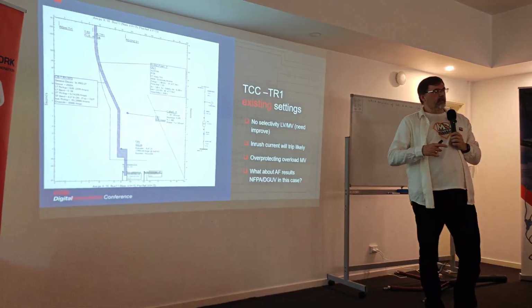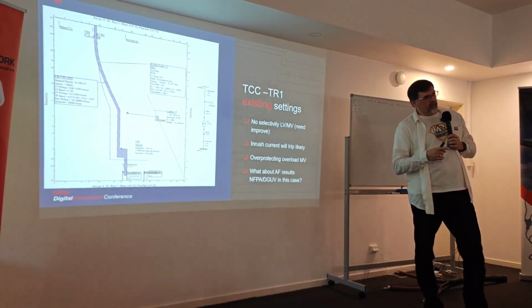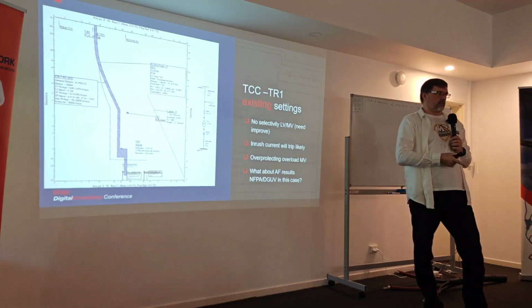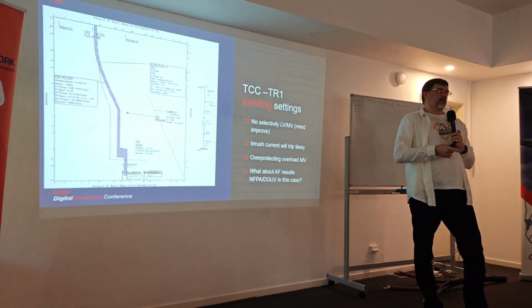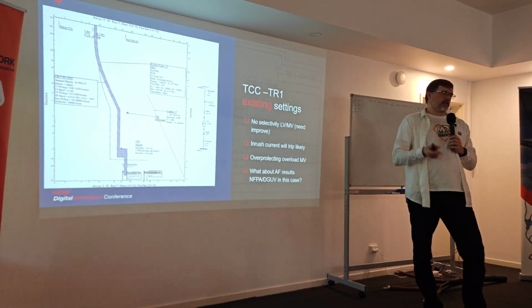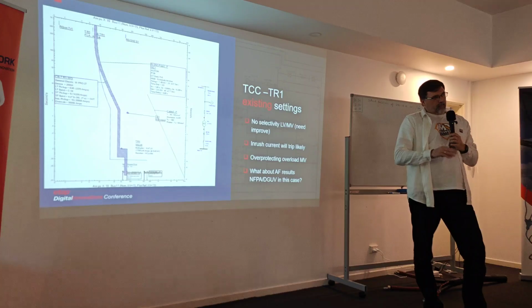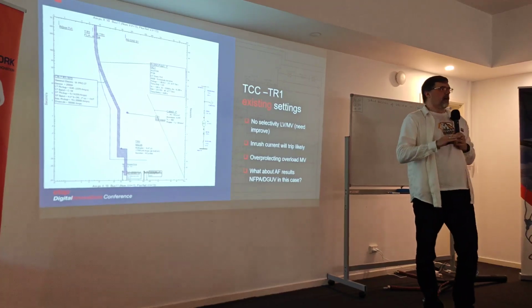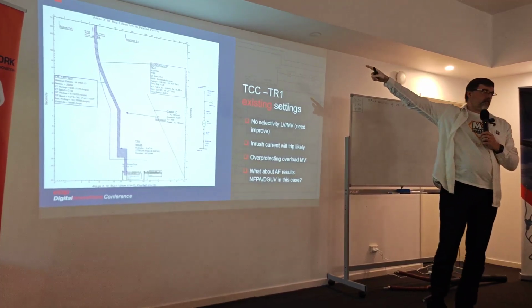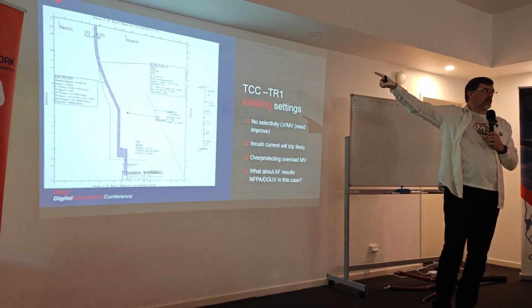My approach is that I try to make the protection correct, and then we look at the arc flash. On most projects, sometimes the customers will say, no, Martin, it's more important to reduce the energy. So I have to double check that they are fully aware that they might be going to the medium voltage station 200 meters away to re-energize.